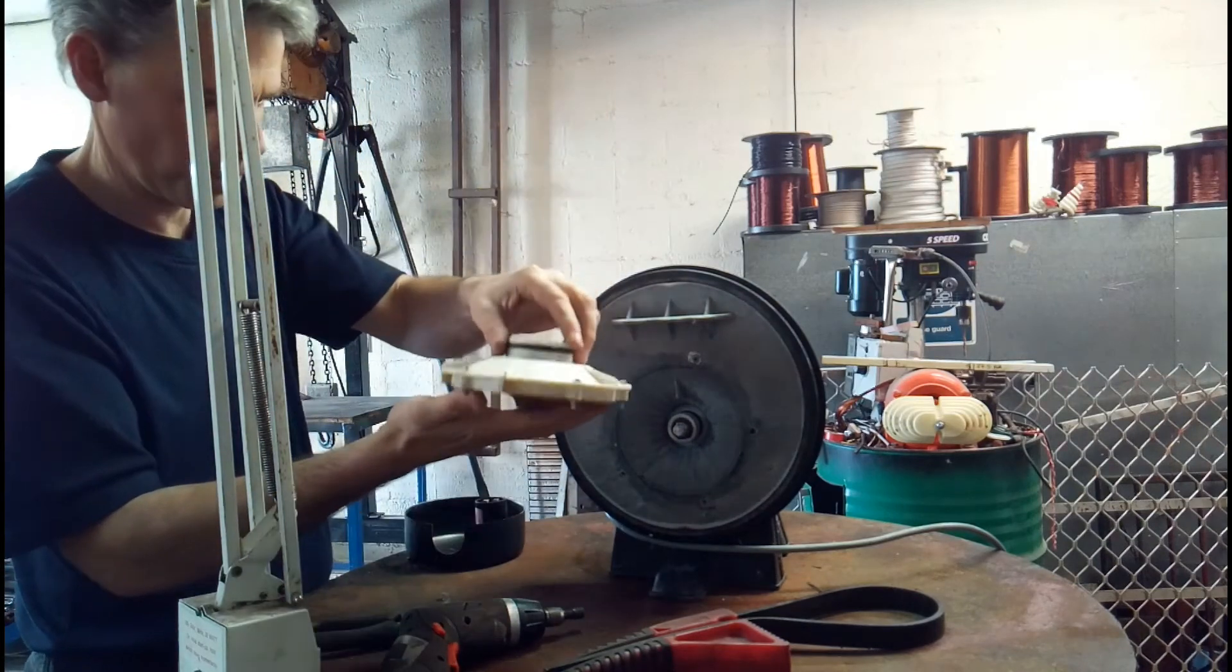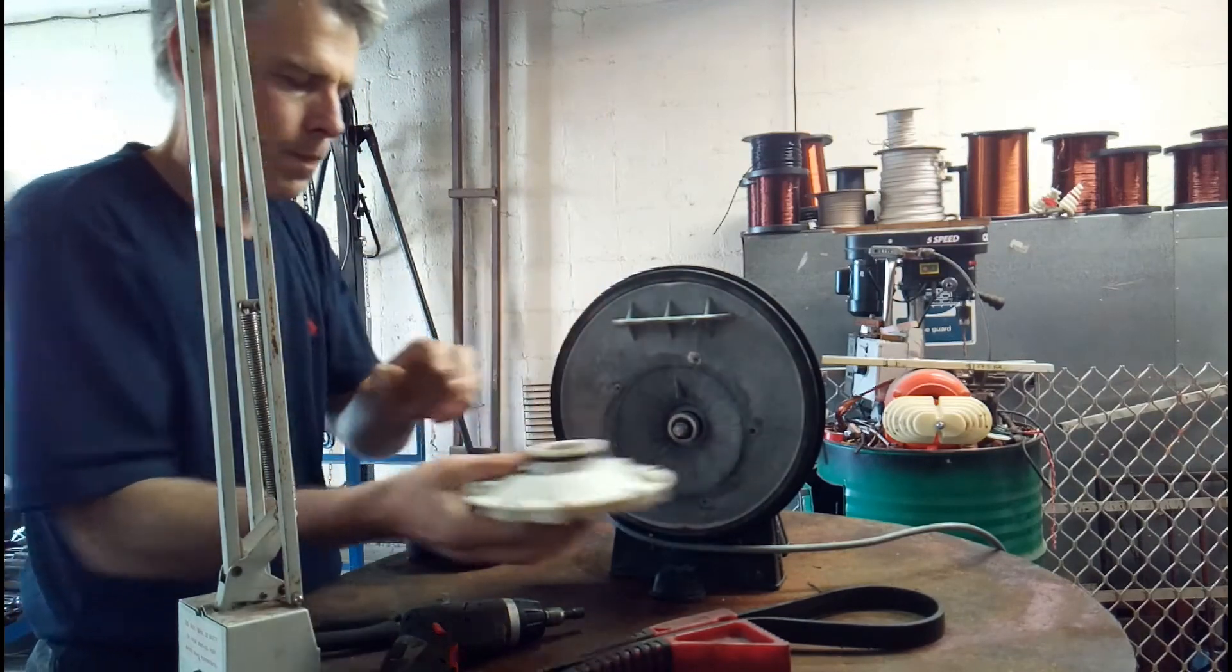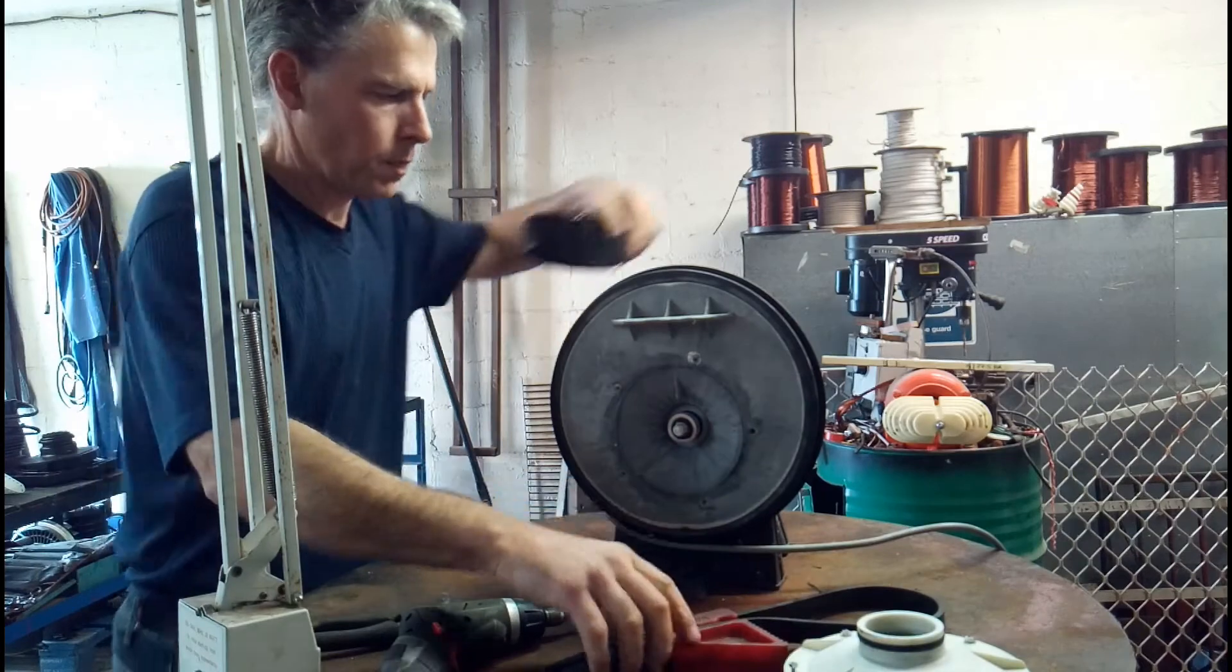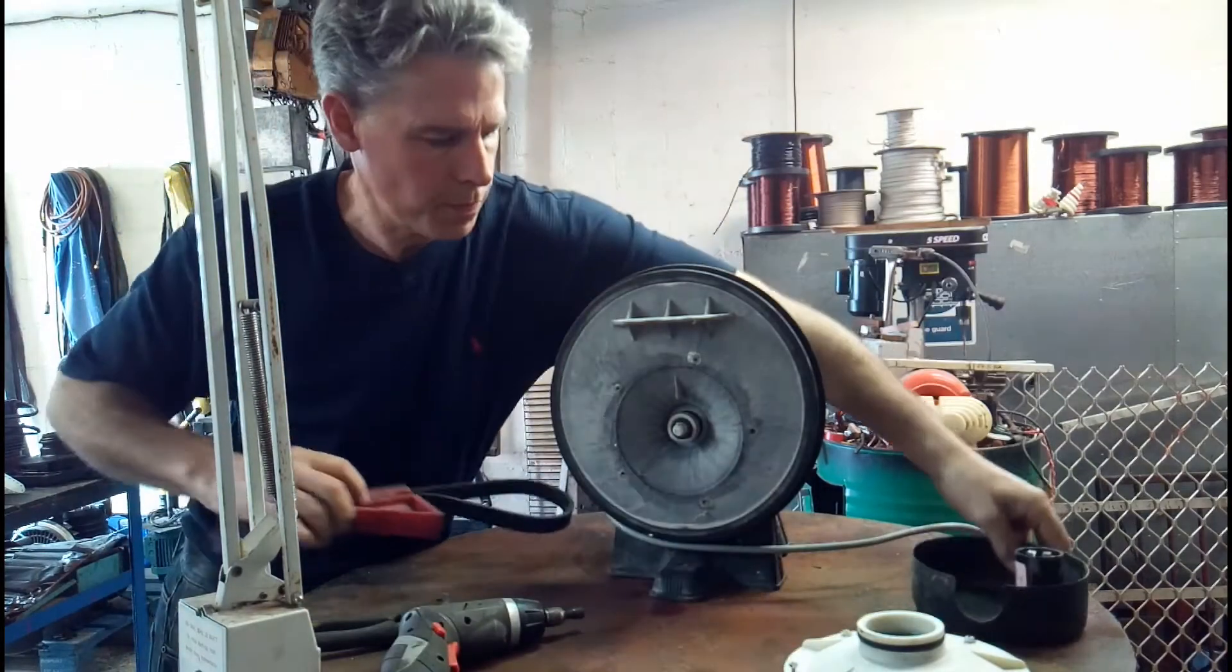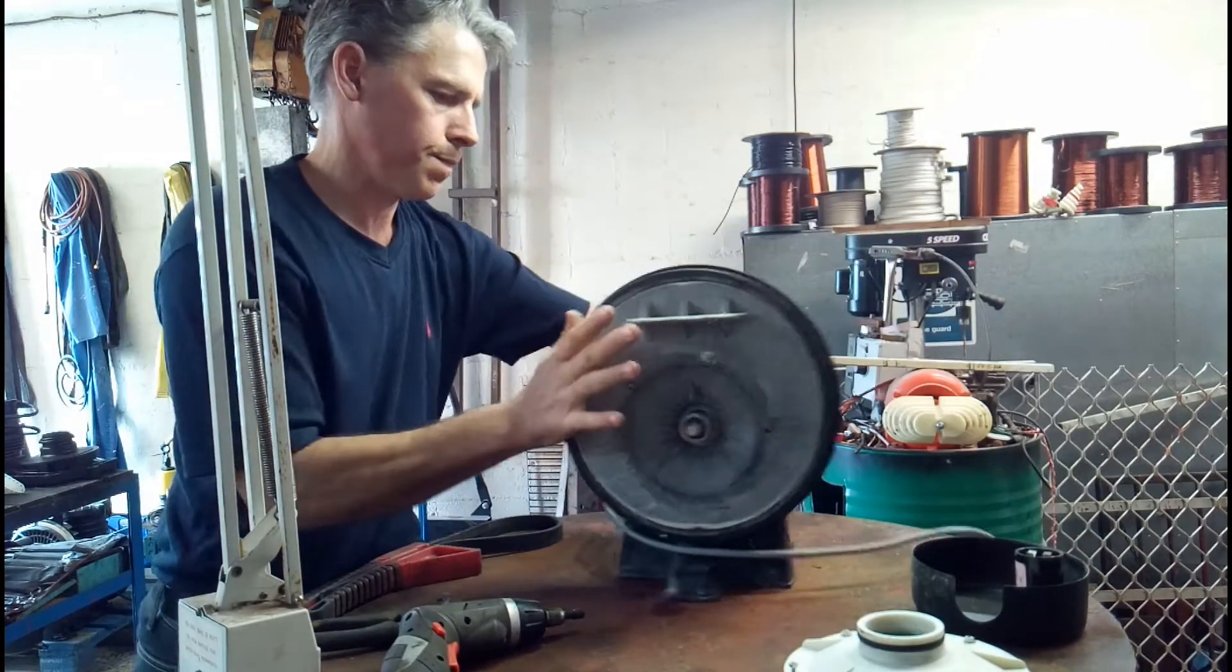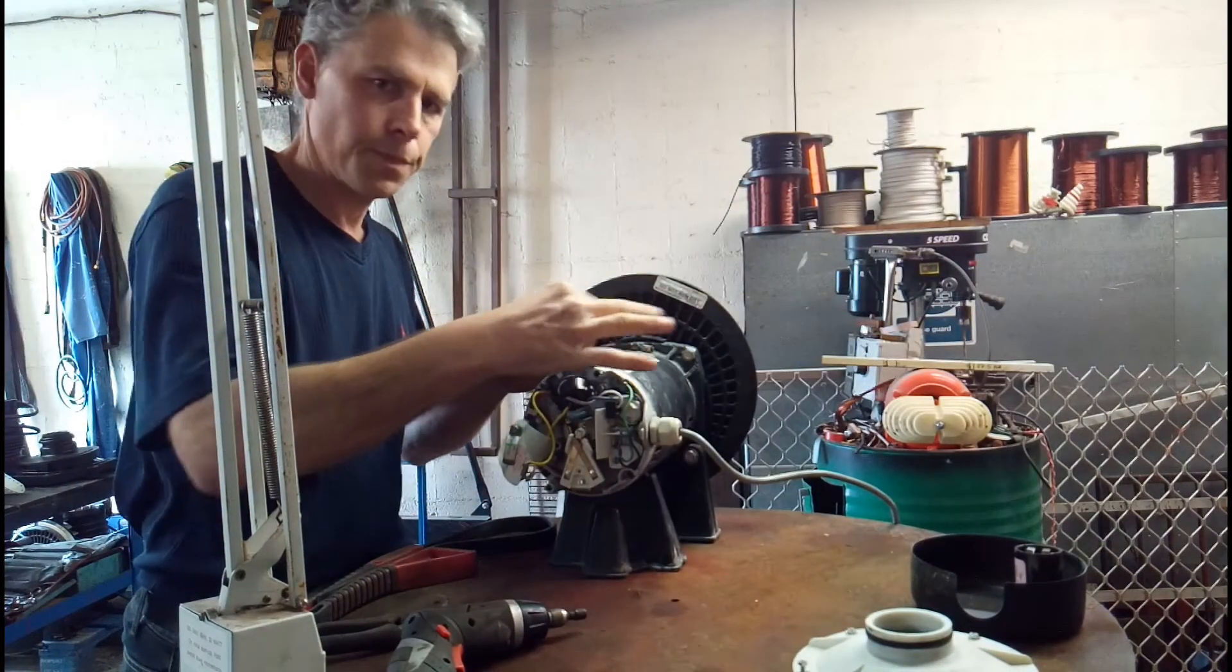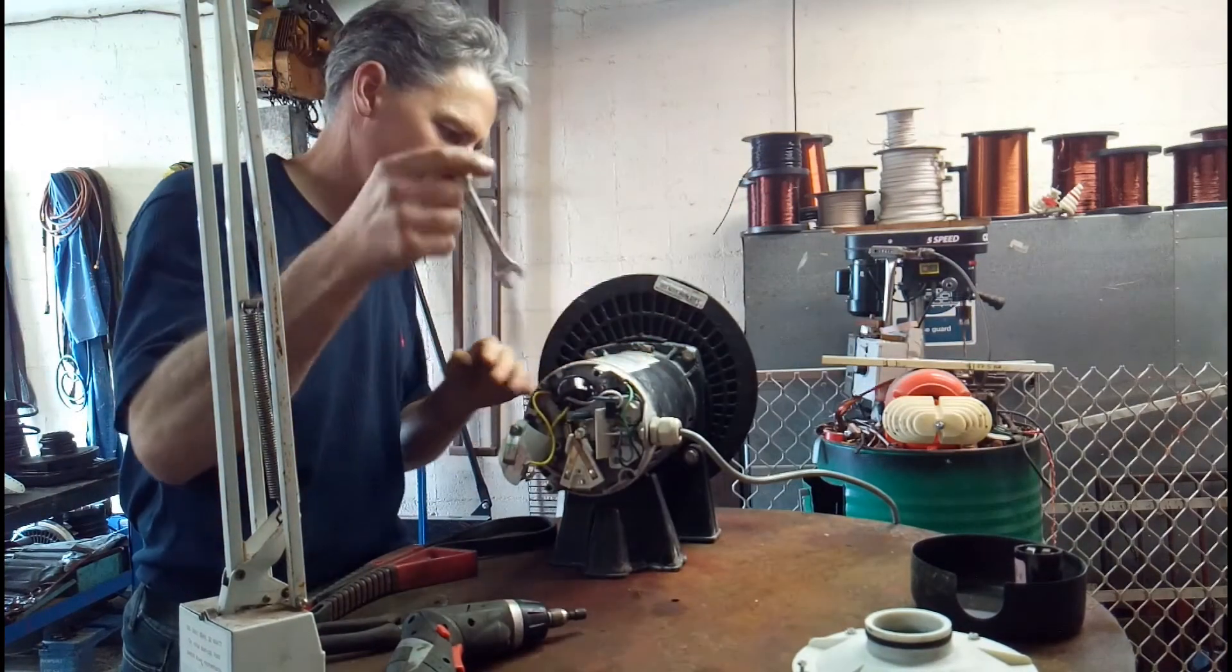The back of them can rust and thereby the seals will not sit straight. So make sure that they are not too corroded and rusted.